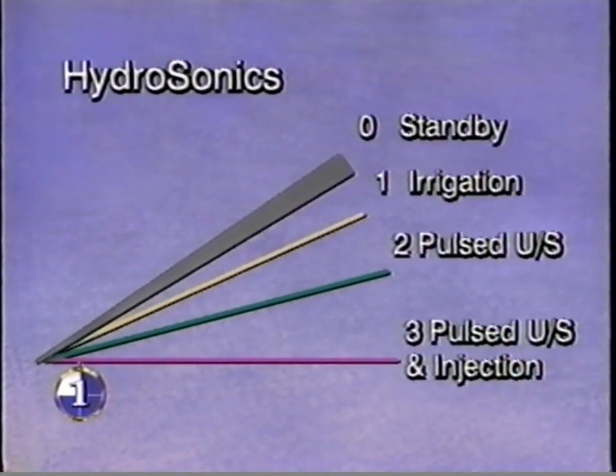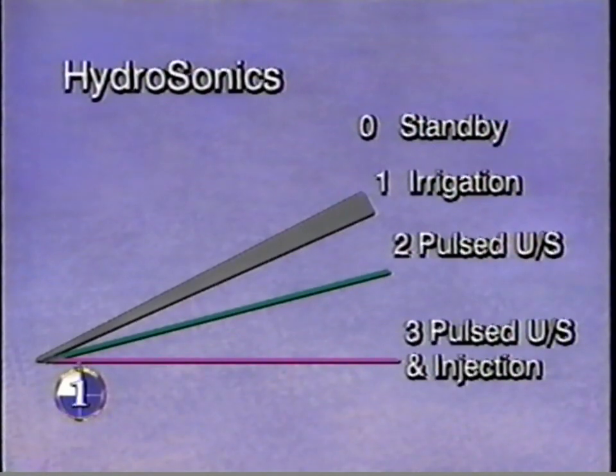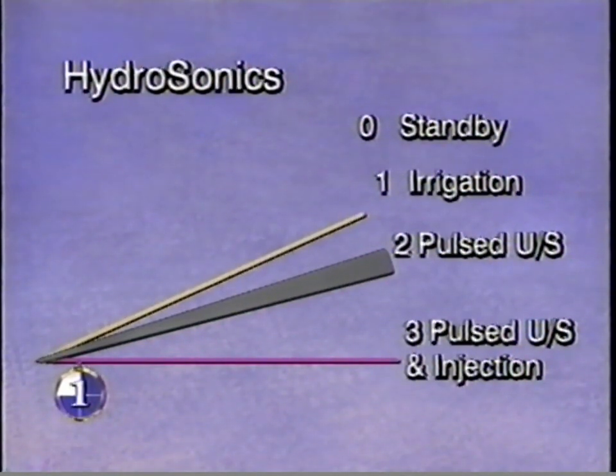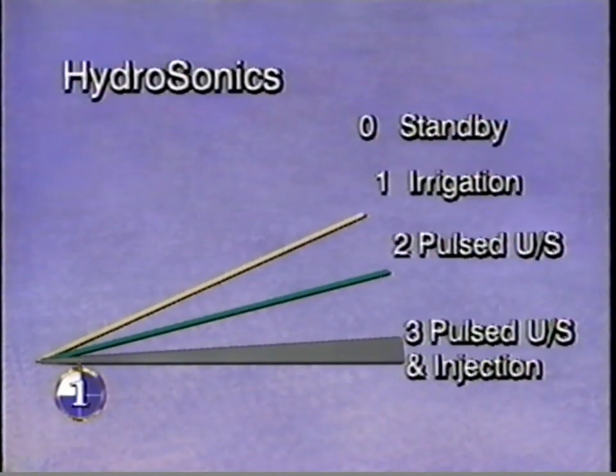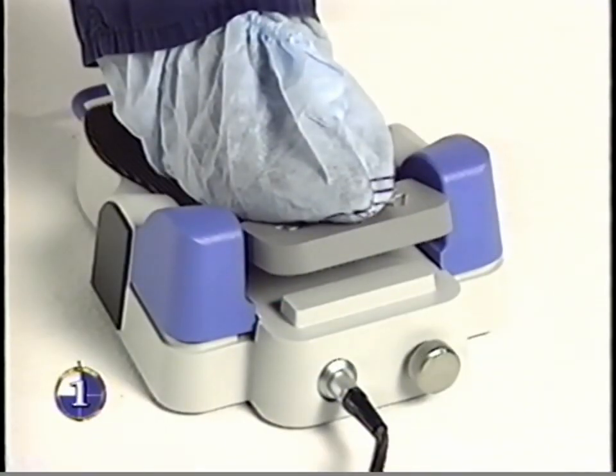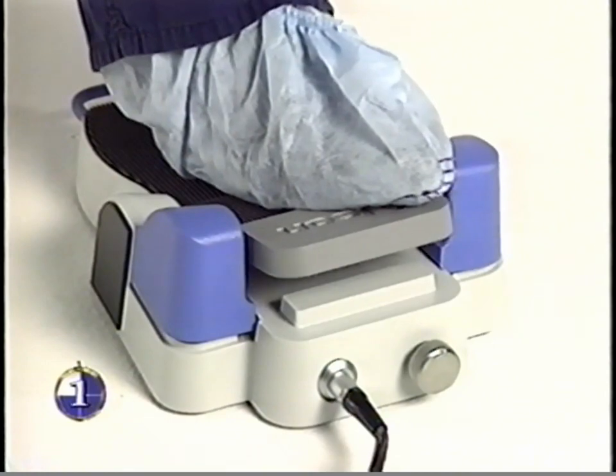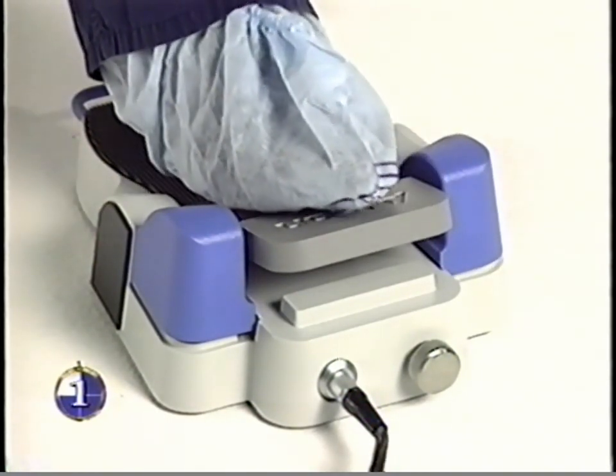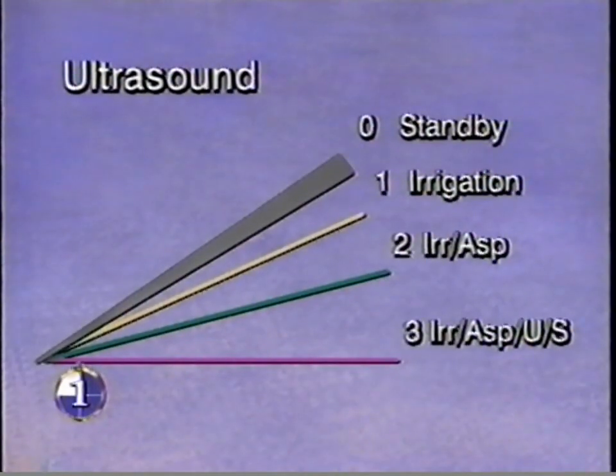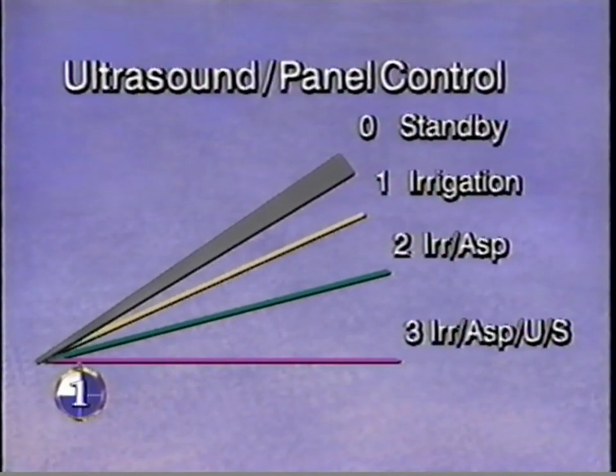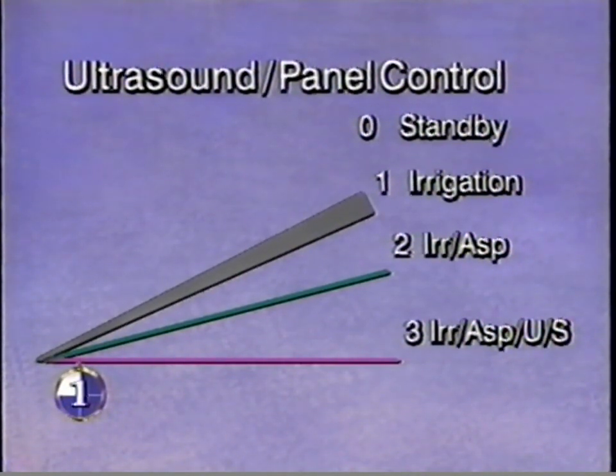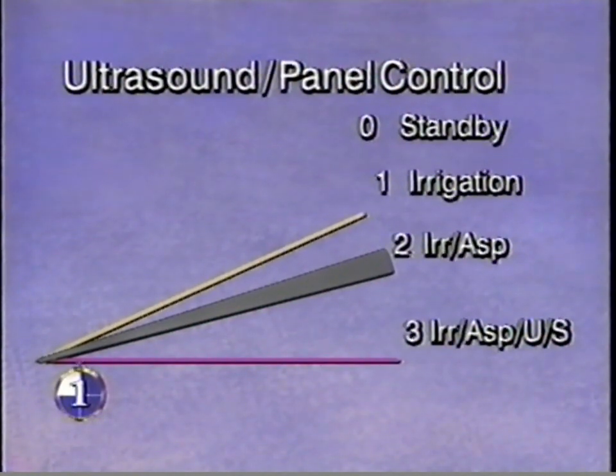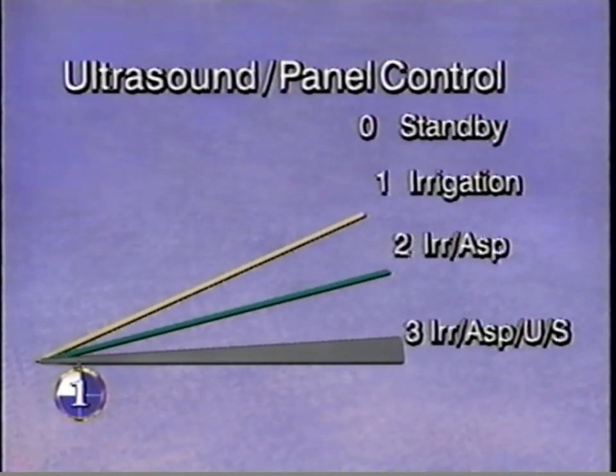In the hydrosonics mode, position 1 is irrigation. Position 2 is pulsed ultrasonics. Position 3 is pulsed ultrasonics and pulsed injection. For pulsed injection with no ultrasonics, depress the reflux switch on the left side of the foot switch. In the ultrasound mode, foot switch functions vary between panel control and surgeon control. Under panel control, position 1 is irrigation. Position 2 is irrigation and aspiration. Position 3 is irrigation and aspiration with fixed ultrasonics.